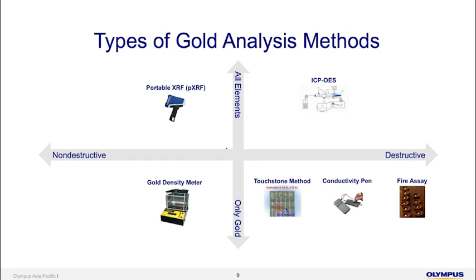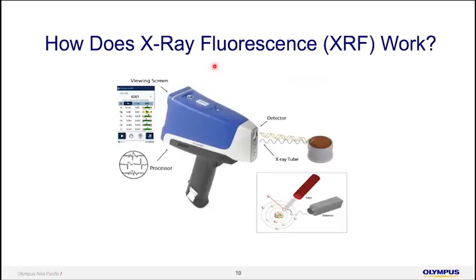Last but not least, we have portable XRF technology. With XRF, number one, it is non-destructive — no sample preparation is required, you do not need to polish your sample. You can test immediately and it will provide you with the full elemental composition of the material. XRF works by having the X-ray tube send out an X-ray, which kicks out the innermost electron of an atom. The nearest electron then replaces the one kicked out, and when this happens, a unique fluorescent signal is created. Our detector captures this unique fluorescent energy, processes it, and we get the elemental composition of the sample.